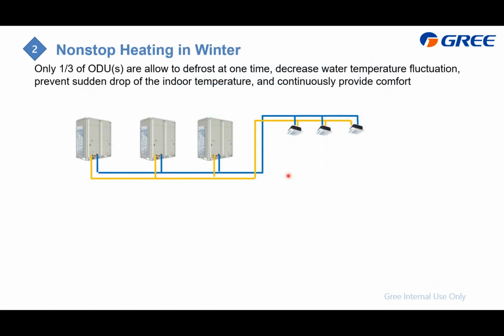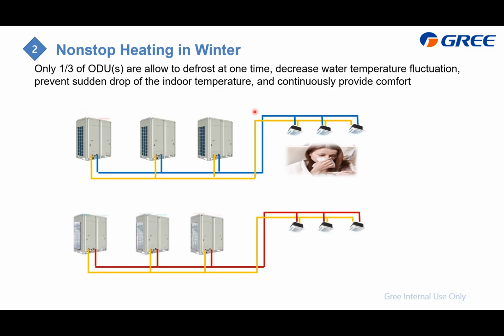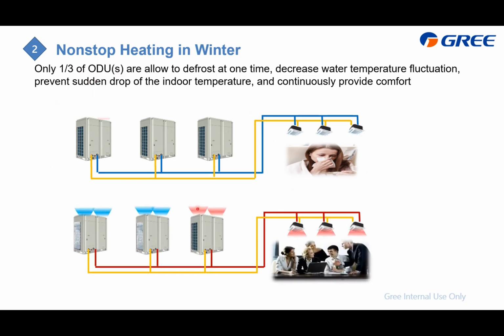And for this modular chiller, in winter, which is in heating, we need to do the defrost if the outdoor ambient temperature is low. And if all the heat pumps adopt the defrost at the same time, then it will make the system inside cold. It will make the temperature fluctuate a lot, which means the customer will not be that happy. And for our modular chiller, we only allow 1/3 of the outdoor units or the heat pumps to adopt the defrost, and after that it will just take turns for the defrost. For this one, we can ensure during the defrost period the temperature of the water will not drop too much or fluctuate that much.